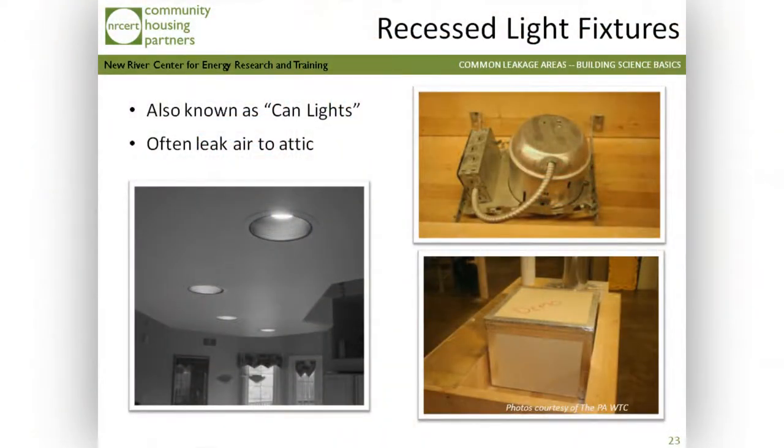And so that's where some people just say, get it out of your way and then air seal everything. That way you can do a much more complete air sealing job and then blow new back in. That's true, but right now while incandescents are still on the market and somebody could change that out, you're better off protecting yourself and not insulating over top, because the IECC code specs out that you can build the box, they're okay with that, but don't insulate over top of it because if ever there is a heat problem inside, that allows the heat to dissipate to the outside.